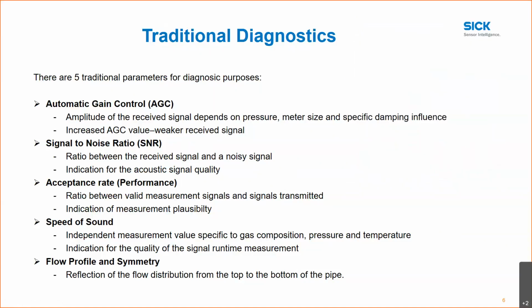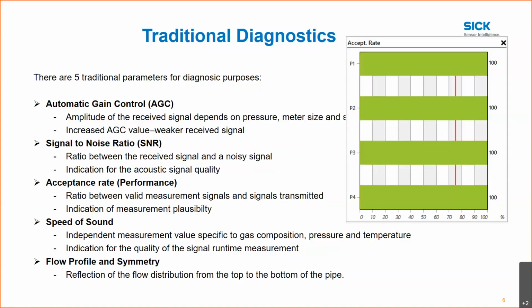Acceptance rate, or performance as it was known in the classic meter, is the ratio between the measurement signals and the signals being transmitted. In other words, if I send out 100 signals between a pair of transducers and I'm able to transmit those 100 signals without any rejections, then my acceptance rate is 100%. So this is a good way of gauging the measurement plausibility, or how many of the signals that I'm transmitting are being received on the other side.